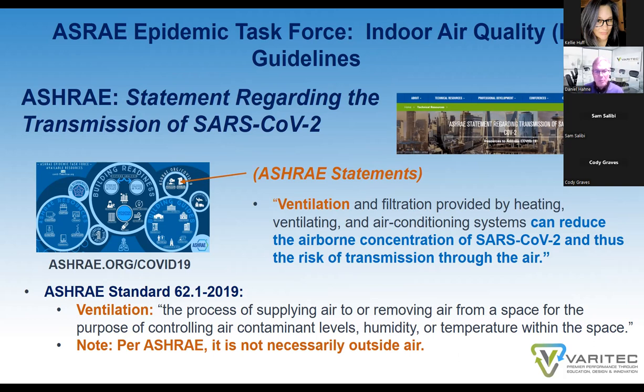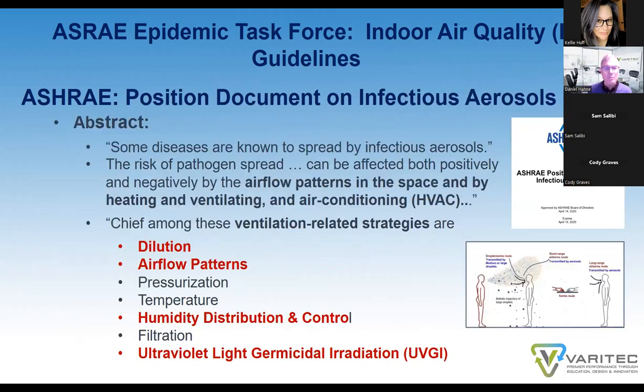ASHRAE Standard 62.1 2019 went on to say that ventilation is an important factor to be considered for reducing the risk of infection. Ventilation is defined as the process of supplying air to or removing air from a space for the purpose of controlling air contaminant levels, humidity, temperature within spaces, etc. And please understand, though I've seen it misapplied, that ventilation air in a room is not necessarily only the outside air. It's comprised of conditioned, filtered return air and outside air. It's a mixed air condition in most circumstances.